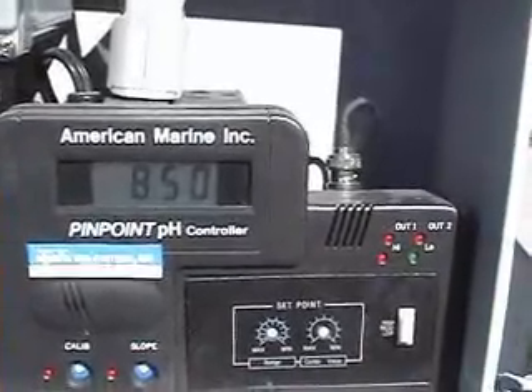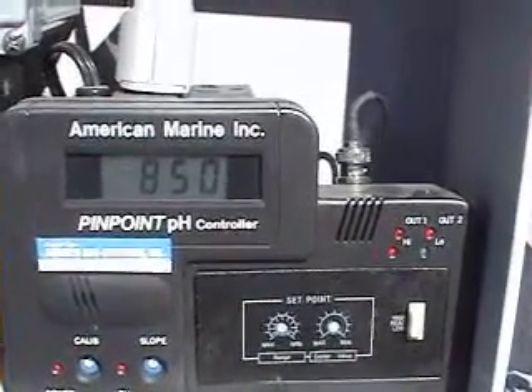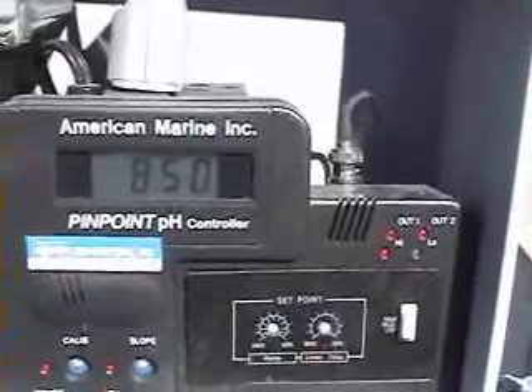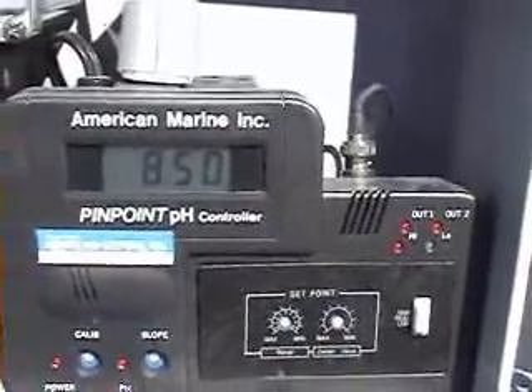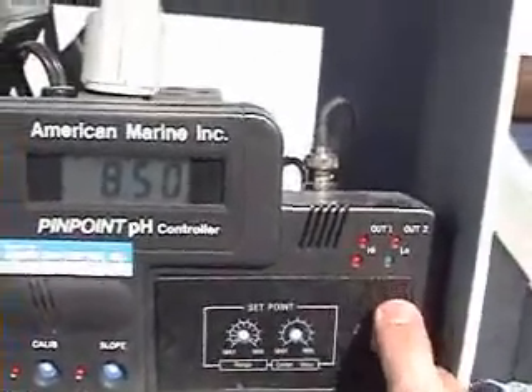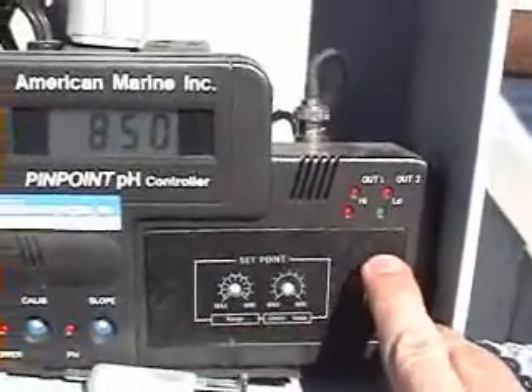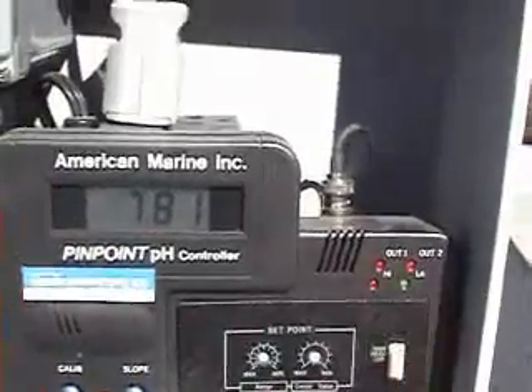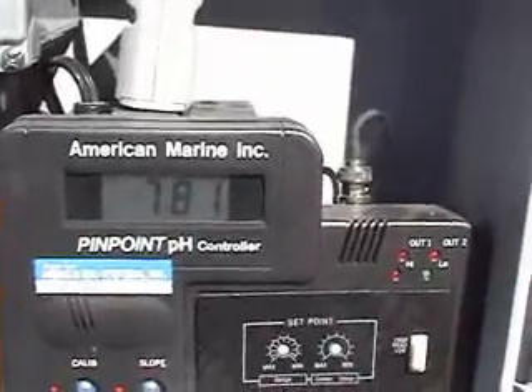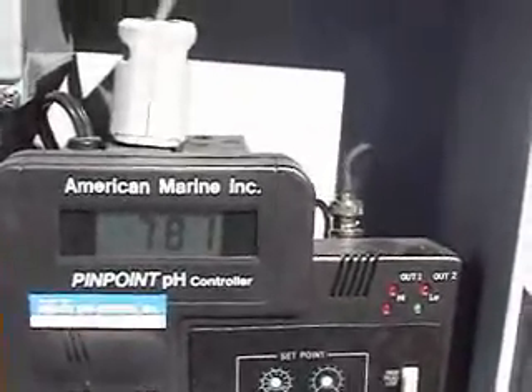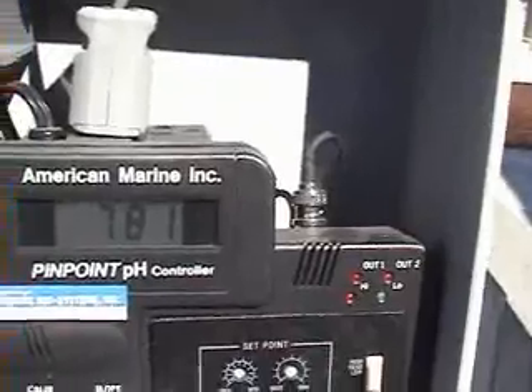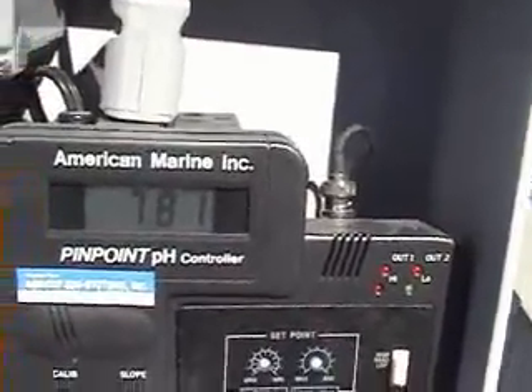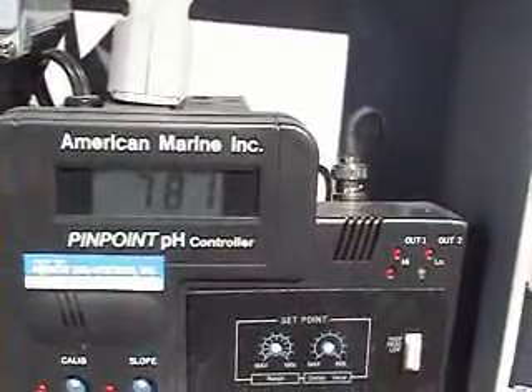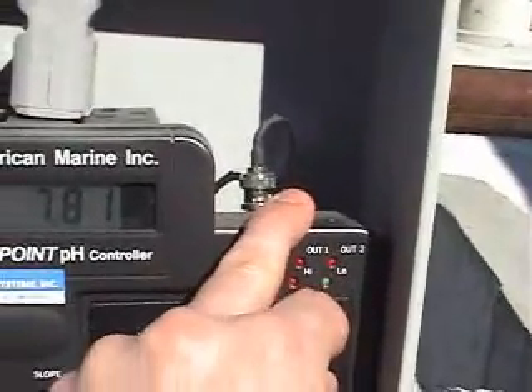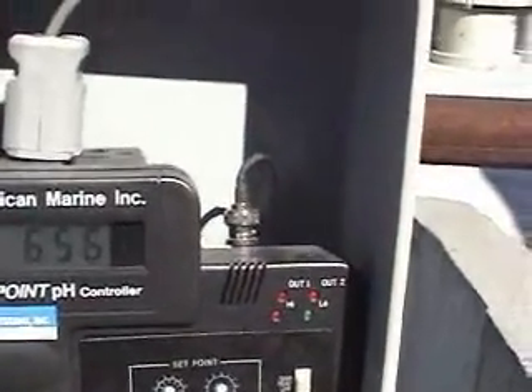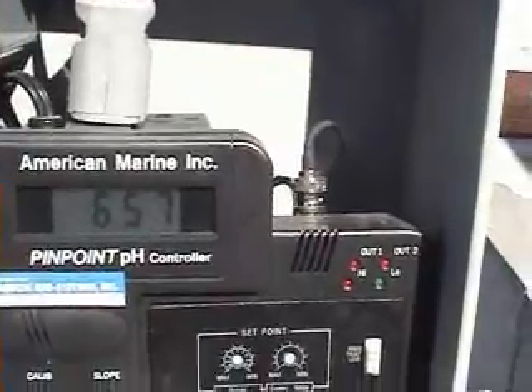So when our pH controller and probe actually sense a pH of 8.5, the system relay will trigger it and actually turn the system on. If I push this button down here, it'll take us to our low setting, which is 7.8. When the pH system receives a pH of 7.81, the system will actually be shut off. And again, we're at about 6.5 right now.